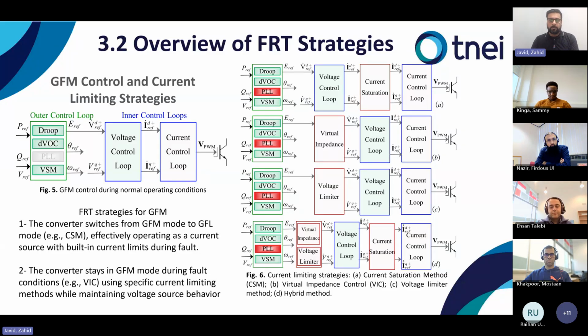The droop control, DVOC and VSM are designed to operate during normal and emergency conditions, as they provide GFM functionality inherently by regulating the voltage magnitude, frequency and synchronization under all operating conditions. But the PLL is generally not used during normal operating conditions and is only activated during an emergency, like during faults or black start operation.